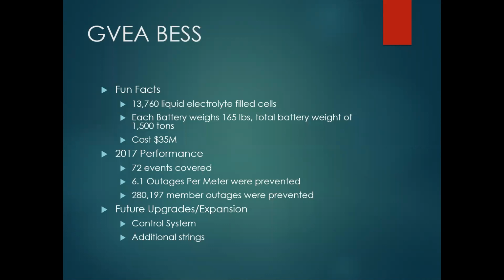However, those 72 events don't cover the small events. You can think of it as the control system having a small bandwidth where it's constantly operating, called the power system stabilization mode. Little things happen around -- if a couple distribution breakers open up, you get a power swing in the system, and the BESS will respond within a tighter frequency band. That's not counted in the 72 events; that's happening continuously. The 72 events is when it exceeds the larger bandwidth. So there's a certain amount of regulation going on just under the radar.